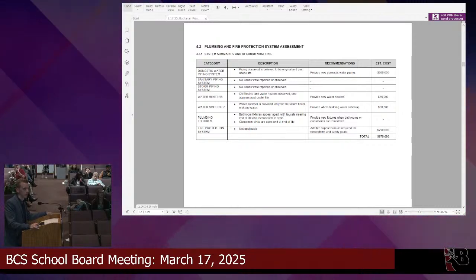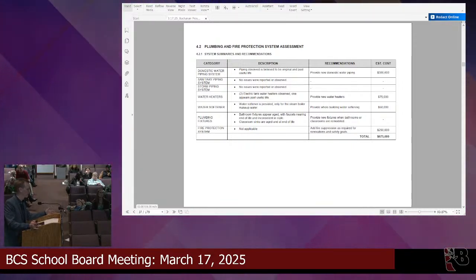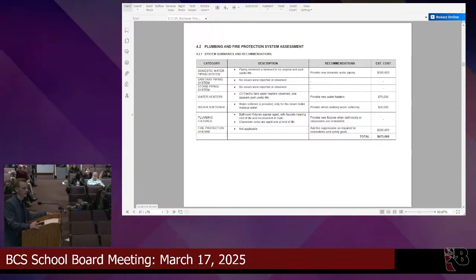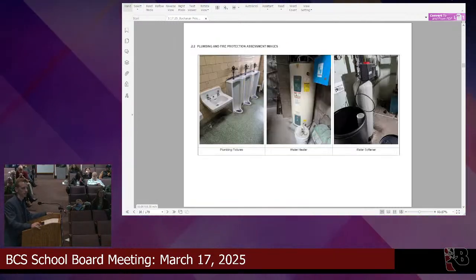From a plumbing standpoint, given the building's age, this is one where we'd recommend your domestic water piping, which is galvanized, is probably corroded a lot. It's going to be time to consider new piping that's more accessible, like copper, as a safety element. And then just some old equipment, water heaters, and adding water softeners, since there's hard water here. You mentioned fire suppression already. A few pictures of the components in there. We've got old bathroom groups and fixtures, these are pretty old, but when you renovate the bathroom you probably want new fixtures.